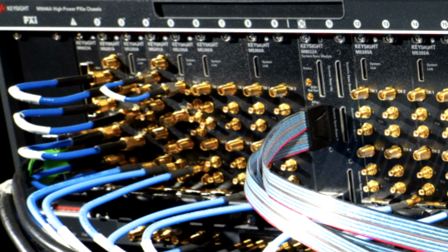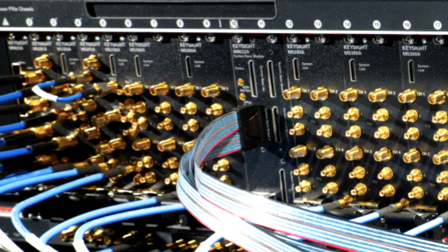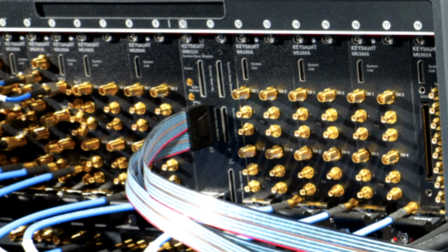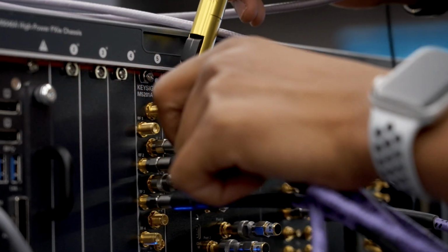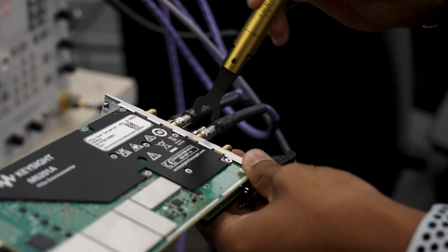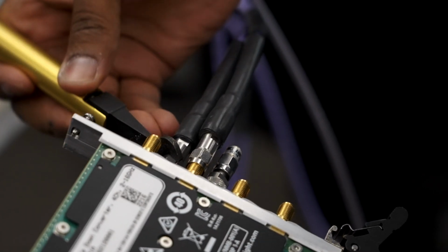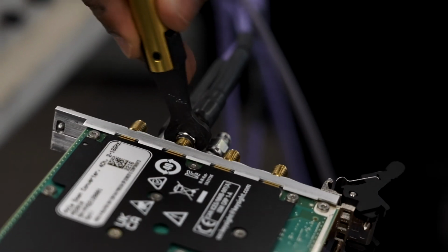A key piece of technology that we're using is a clock module developed by Keysight Labs that's a very low phase noise clock reference. We were able to leverage that technology and put that into this system, and that gives us very good long-term time stability. And then we take that as kind of the source clock for our time base, and then we multiply that up in frequency to drive all the samplers and our digitizers and our AWGs. And we do that through specially designed cables that don't drift with temperature and circuits that are designed to have very low phase noise and low phase drift. And all of that contributes to maintaining low jitter in the system.